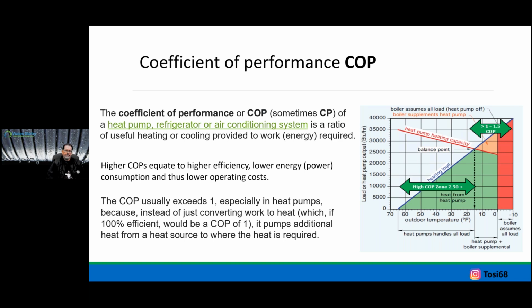The chart to the right is showing you our heat pump heating capacity, right? There's something with an arrow saying balance point. Eventually, we will degrade or reduce the output because of our limitations with refrigerant. It's a natural thing. It can only take us so far, but it could be upwards of 200% efficient until that point. And then we might need some kind of backup, right? And we do have modern day heating now with just that.